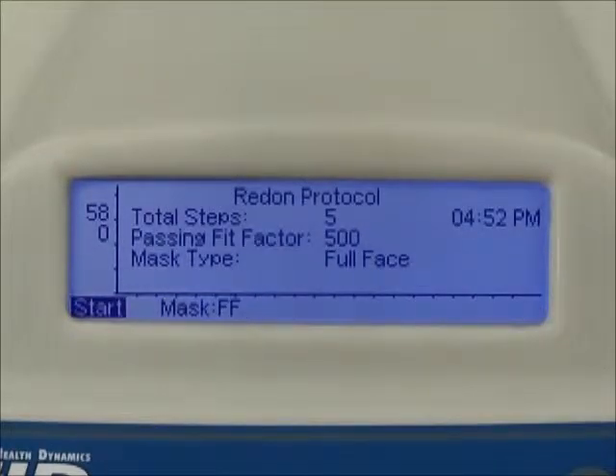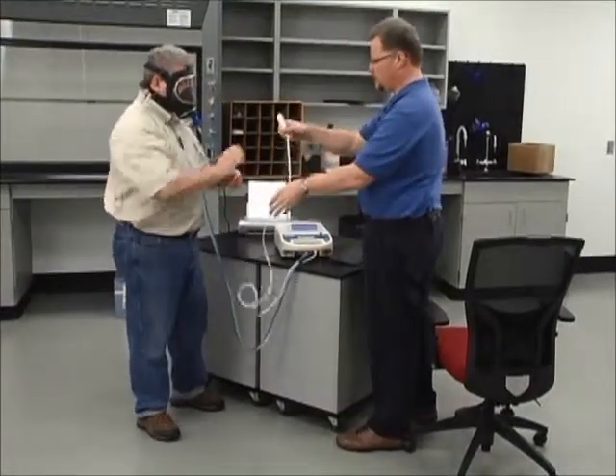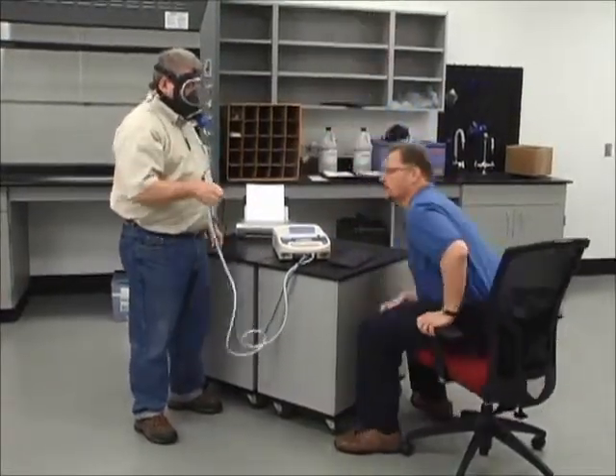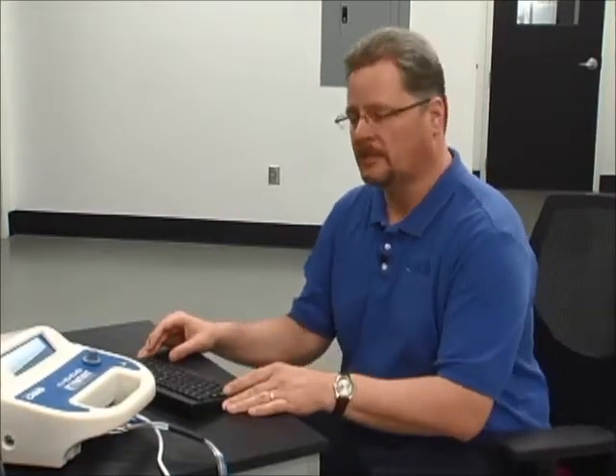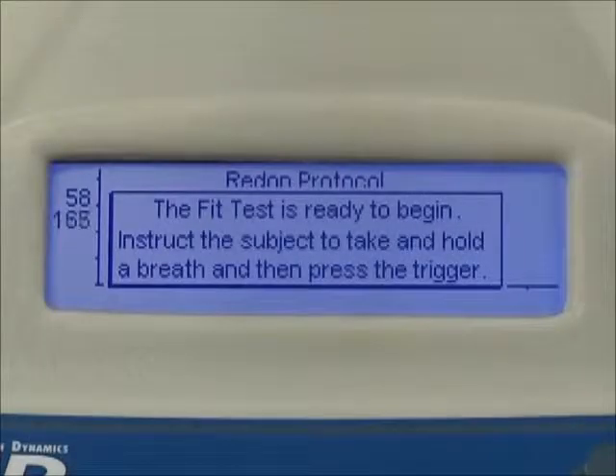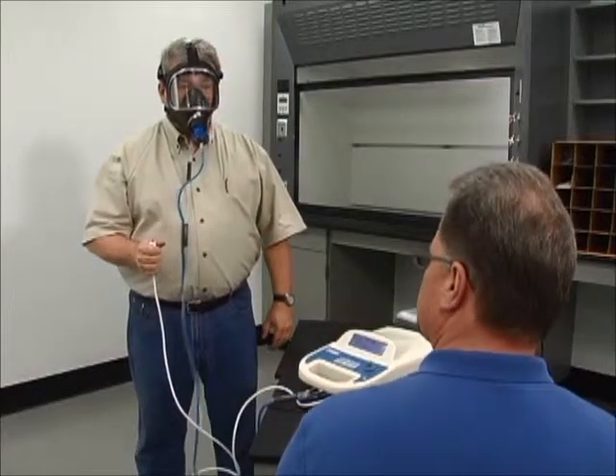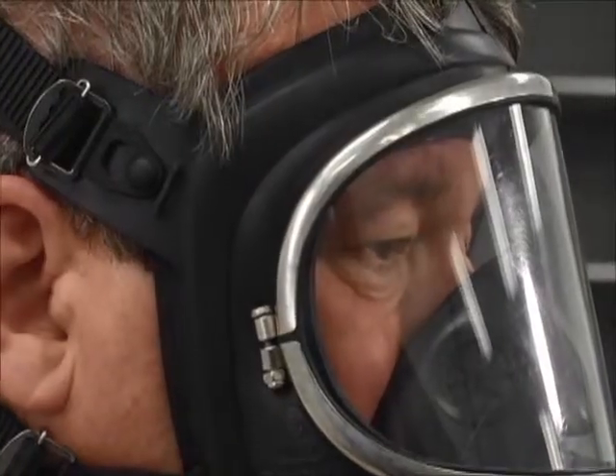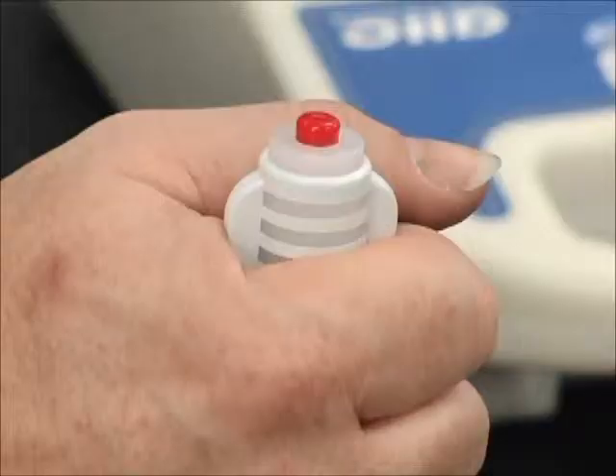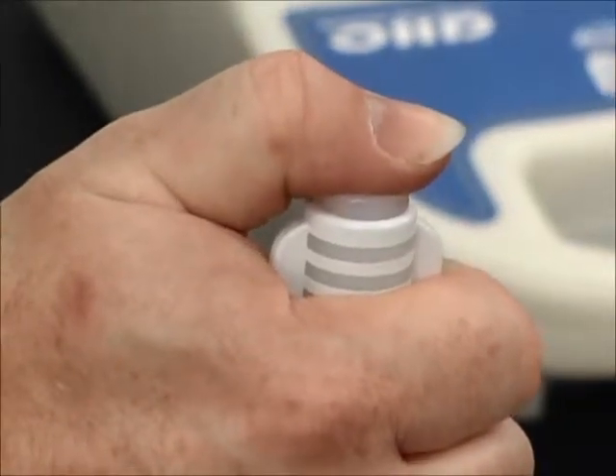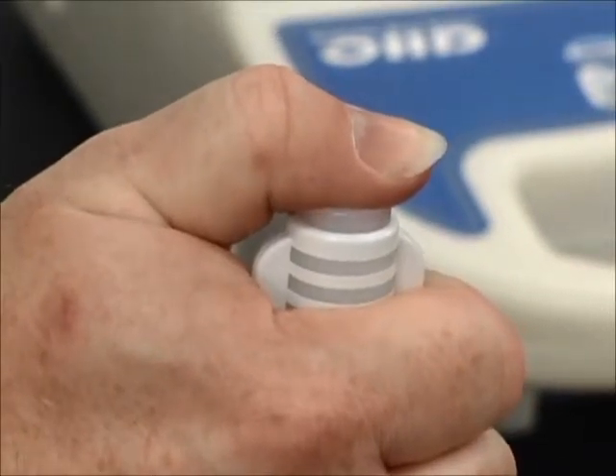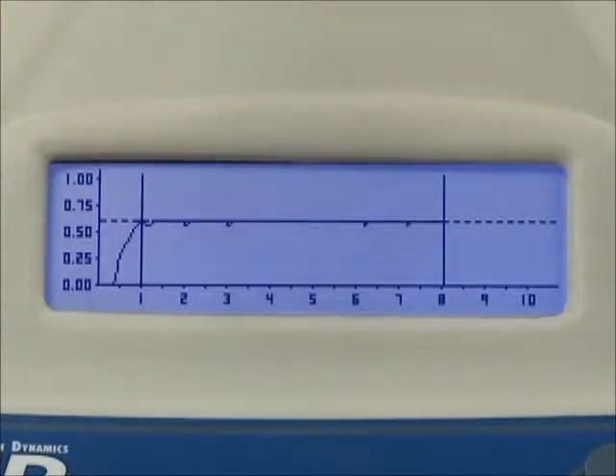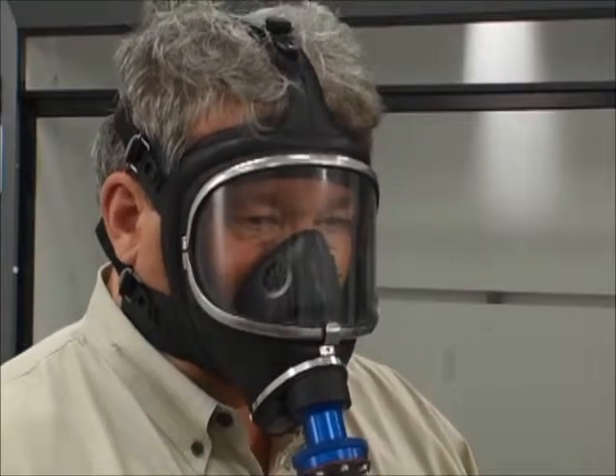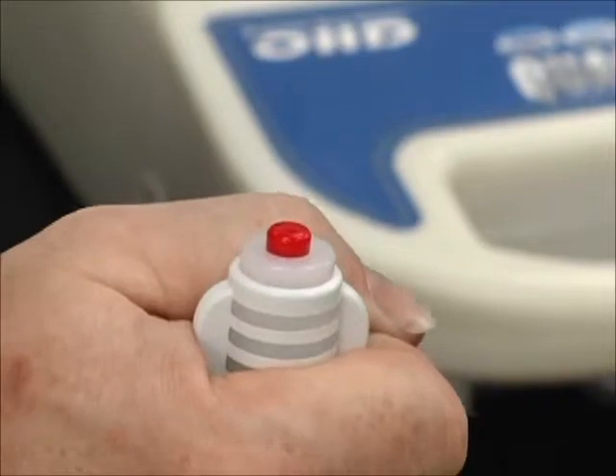The test subject will stand as still as possible and face forward as instructed in the first step of the protocol. Instruct the subject not to breathe, exhale, or swallow, but remain completely still until the test is finished. Explain that he will take a comfortable breath, not a deep breath, and hold it during the 8 seconds of the test. When the test subject is ready and is holding his breath, he can press and hold the trigger button until the test has been completed. At the end of the 8-second measurement, the valve will automatically be released and the test subject can breathe normally. At this time, he can release the trigger button.